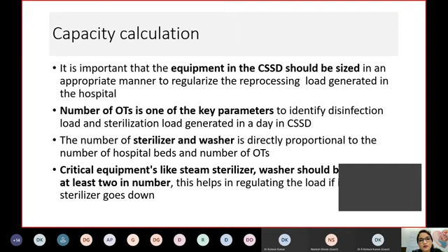Rather than that, you go for 2 smaller ones, and you add them up, which takes care of your total capacity, because if one runs down, you have a backup available. And sometimes you may not have so much workload at one go, and you don't have to run your big sterilizer every time. So this will be of great help when you're calculating your capacity requirements.